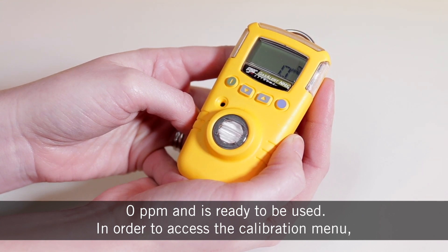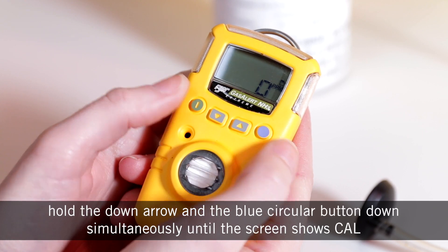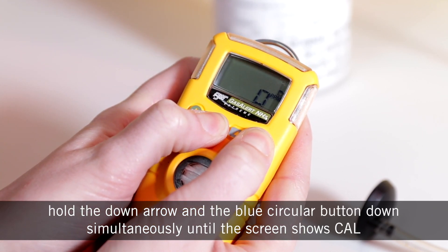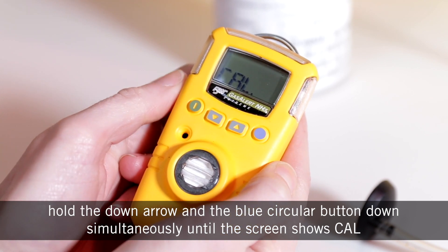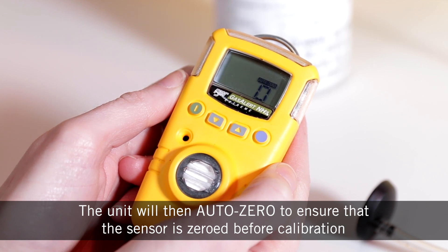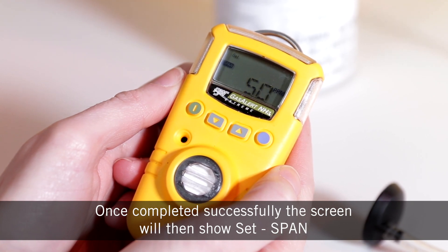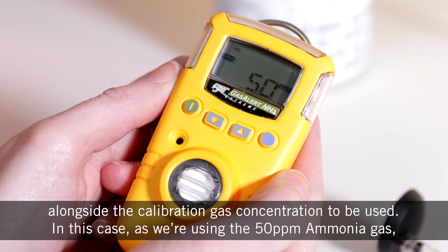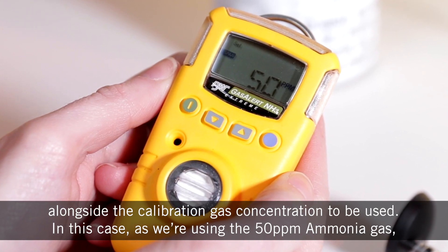In order to access the calibration menu, hold the down arrow and the blue circular button simultaneously until the screen shows 'cal'. The unit will then auto zero to ensure that the sensor is zeroed before calibration. Once completed successfully, the screen will then show 'set span' alongside the gas concentration to be used.